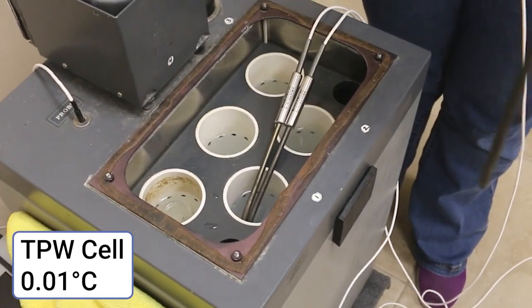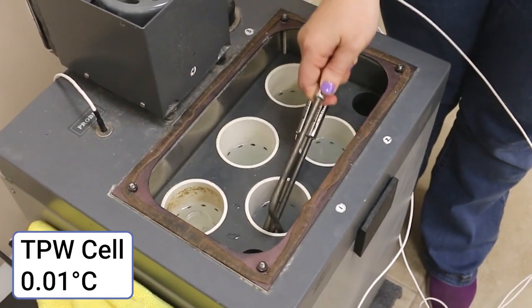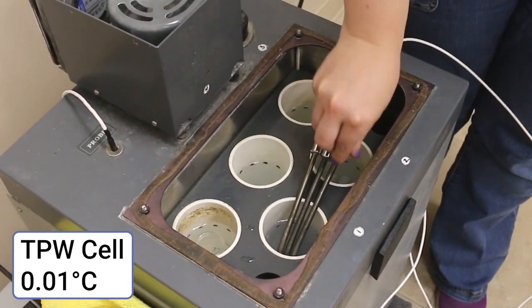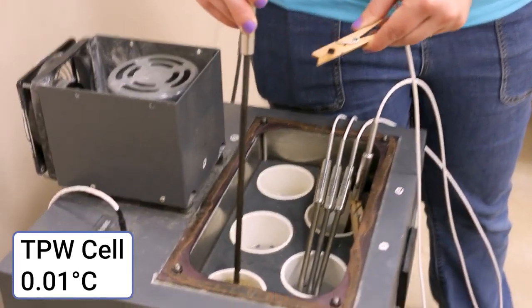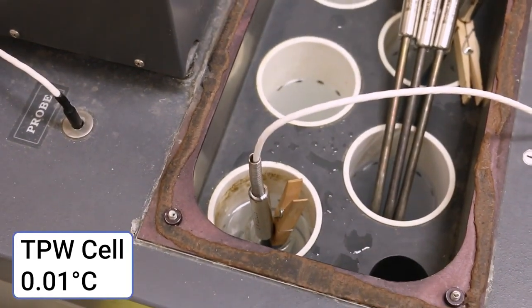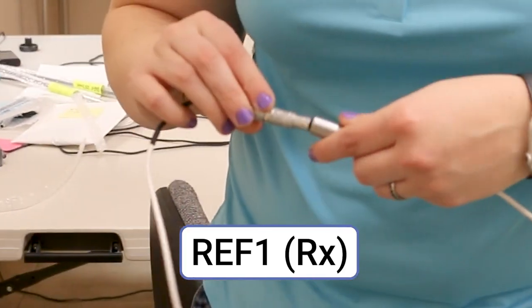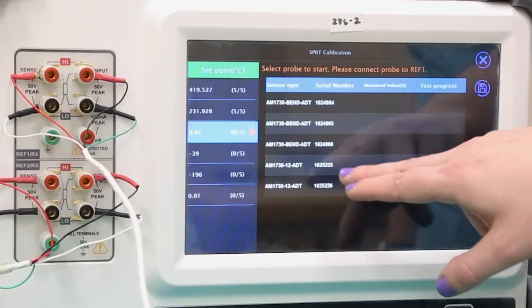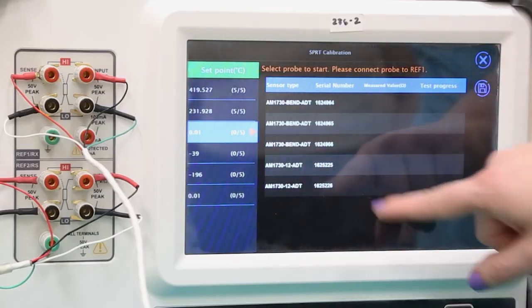Since we can confirm the triple point has been reached with a visual inspection of the cell, we don't need a check standard for this calibration point. For this set of measurements, we'll start with the straight probes first. Move the active probe into the water cell, then connect the cable to the 4-wire connection on REF1. On the 286, select probe 4 from the menu to begin measurement.